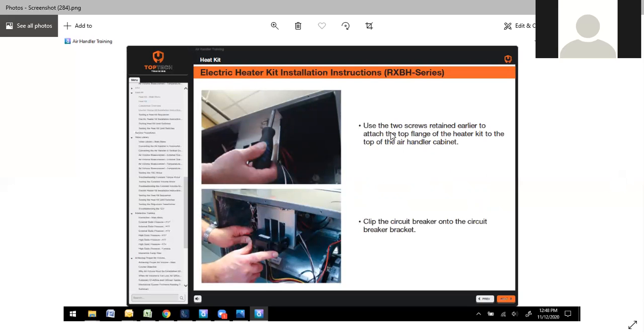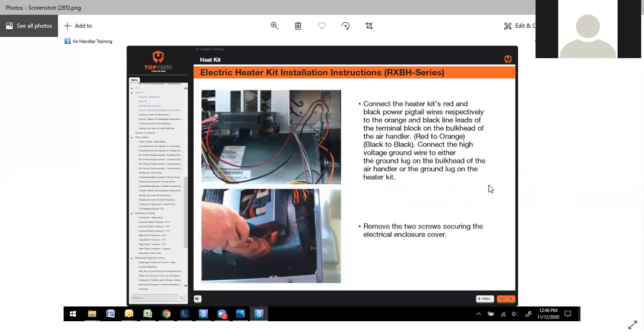I used the 2 screws retained earlier from the blank off plate to attach your breaker plate there, and then clip the circuit breaker onto the circuit breaker bracket. If you've got more than one, clip those in as well. This is a big one here. I've had guys call me before, like, I've got this red and black wire, where do they go? You'll have 2 pigtails coming off the breaker here, a red and a black. It is imperative here that you tag those in. At the top right hand side, you'll have your orange and black from your motor right here, and you'll have 2 empty spaces on top. The red from the breaker should go to the orange, and the black from the breaker should go to the black.